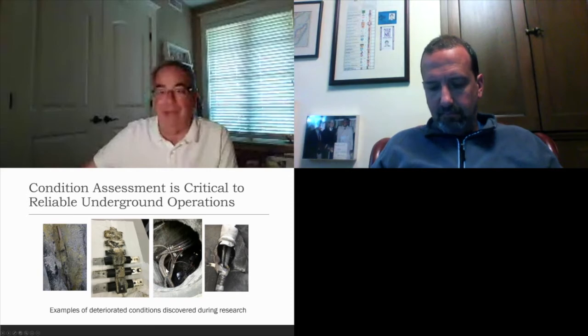And then we block that with the blocking circuit itself, which is kind of like a Bose noise canceling headphone. It listens for our signal, recreates it, inverts it 180 degrees, and re-injects it into the cable. So it's basically virtually cutting the cable at those two points. That allows, of course, no current flow out, and all the current then flows through the shunt capacitor branch.